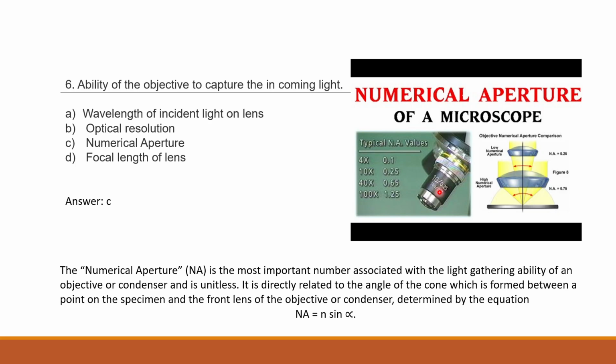So in the objectives you see, every objective will have certain numbers written on it. But you should know what those numbers are. A few of the objective lenses will also write it, like NA is 0.25, this is 0.2, minimum focal distance is so and so. Maybe in a few of the lenses it would be written. But if you get to know what everything is, then if you're checking any other objective, you will remember, okay, this value corresponds to so and so terminology. So like that you should always check the objective.